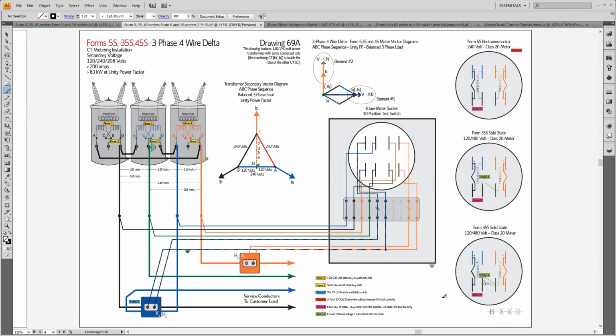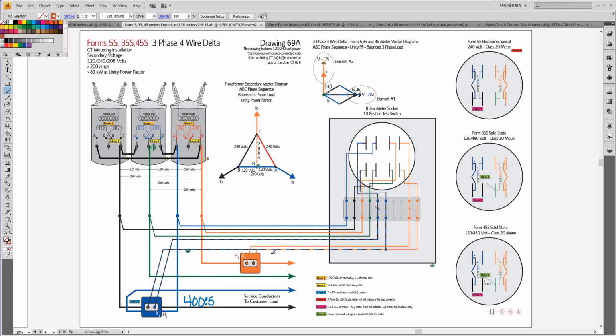So from our 3 energized phases, 2 of the energized phases come off of this blue phase that goes through one way on our CT, and the black phase that goes through the opposite way on our CT. This theory that is sitting right here is the exact same theory that we do with single phase CT metering with a single CT. The other CT is, by CT size, half the size ratio-wise. So whatever this ratio is, if this ratio was, in this case, we'll say 400 to 5, this CT, where the high leg is, would be a 200 to 5.